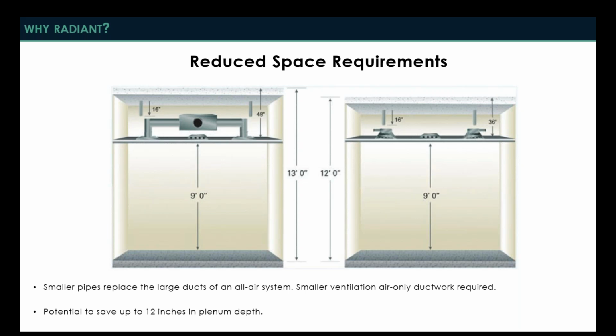So you can see here the image on the left shows what would be more of a traditional all-air VAV type system, where you have larger ducts, distribution from VAV boxes to diffusers, and it takes up a decent amount of space. The image on the right shows much smaller radiant systems. These radiant systems tend to be very thin. You have small size piping that is running above the ceiling, and any ventilation ductwork that is there is just for ventilation only, not for heating and cooling. So the sizes are much smaller. And you can see up to 12-inch reductions in plenum depth when you utilize these types of radiant systems. And everybody knows that in DC, we have very tight floor-to-floor heights due to the restriction of the height of our buildings. So radiant systems can allow the opportunity to have much better ceiling heights than you might otherwise have.